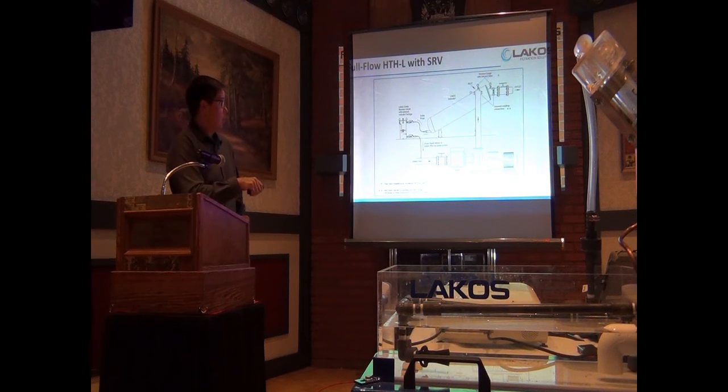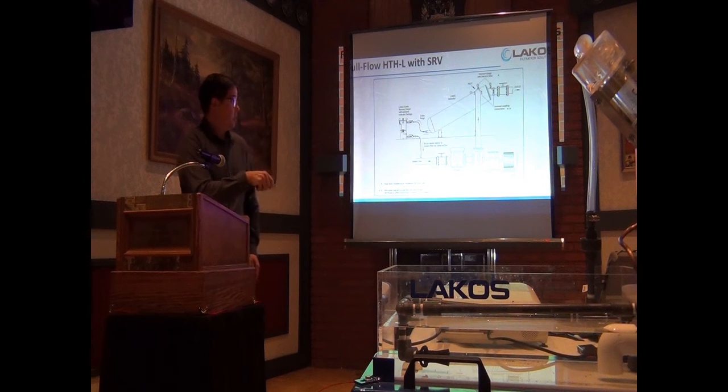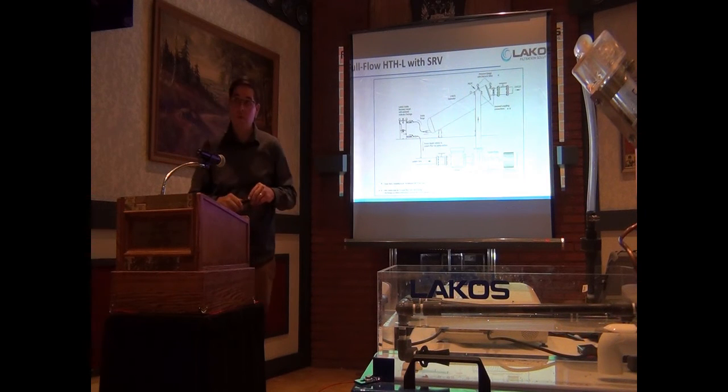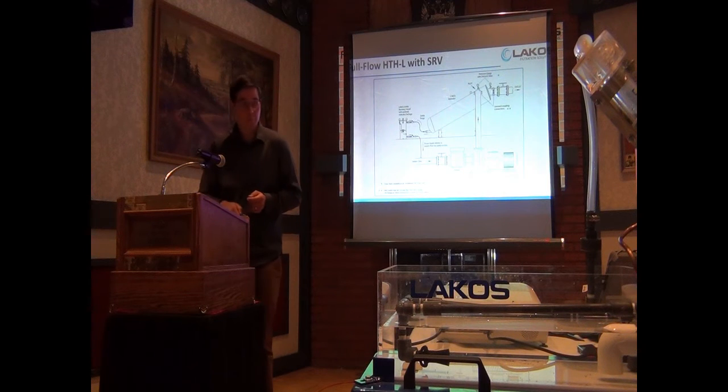And this would once again be a zero water loss option, where we're collecting the debris out of the bottom of your filtration system, collecting it in our solid recovery vessel, and then just providing a line for the liquid to escape back to the negative pressure section here. So when this does get full, we can isolate the flow, clean out your filtration sock that's in that solid recovery vessel, and then close it back up and put the filter back in.